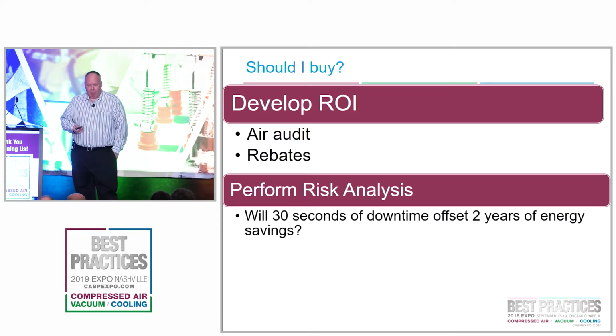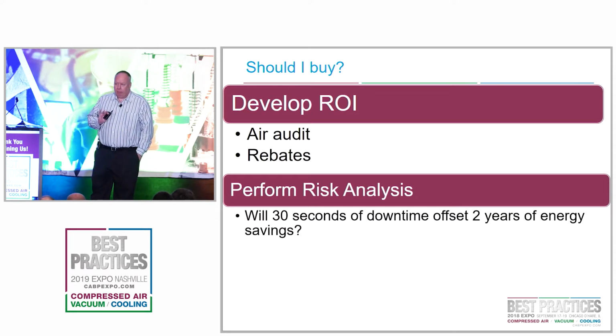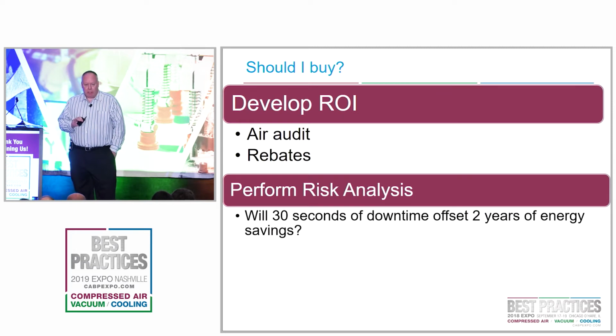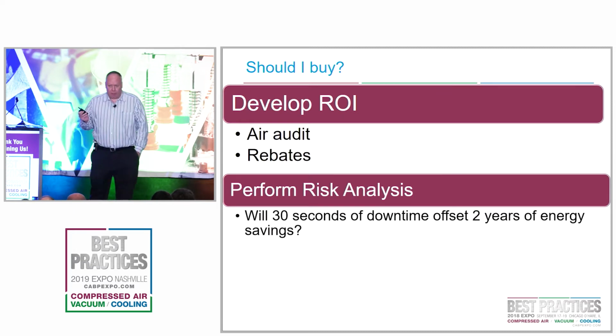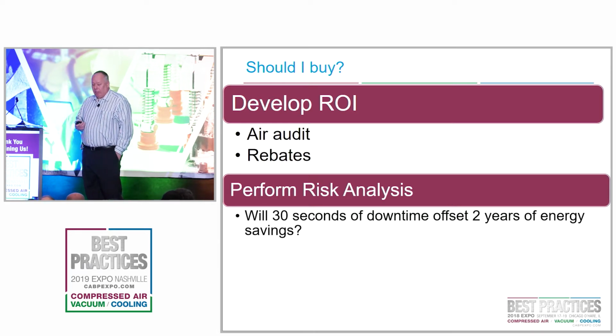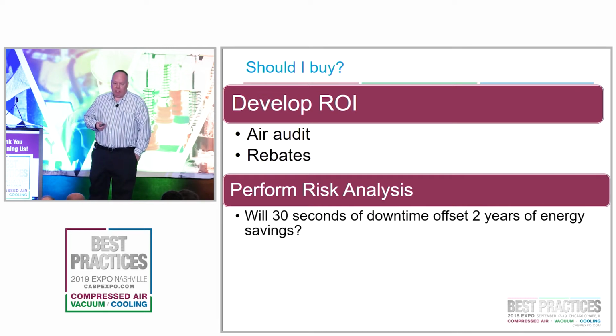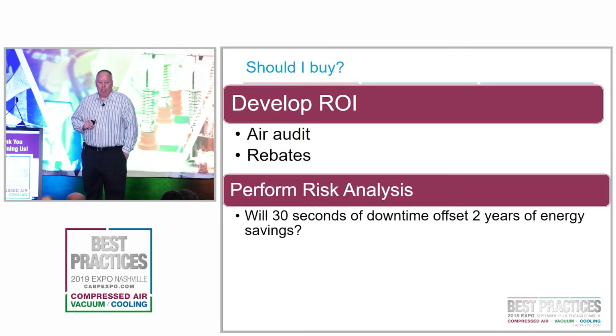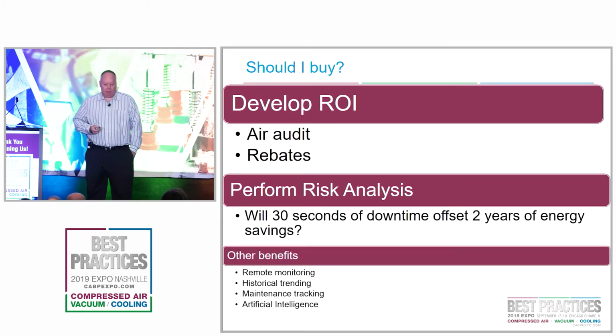And if you implement it properly and do all the proper testing up front, and make sure the system's working as well as it should, then that should not be a problem. But if you're in a facility or have a process where 30 seconds of downtime would offset 2 years of energy savings, I would suggest you think about keeping that compressor running that doesn't need to be running, because the risk of trying to save a few thousand dollars in energy may be outweighed if your control system is not able to bring a compressor on as quickly or at all when you need the air.